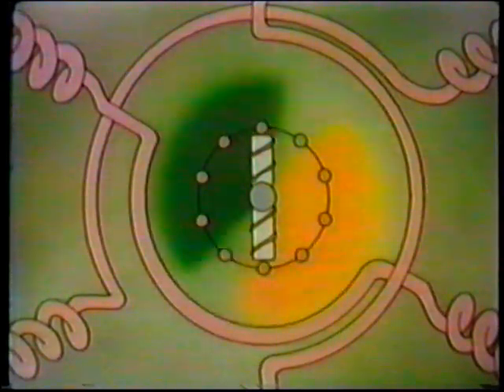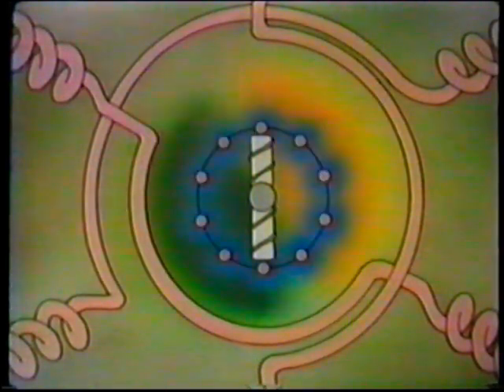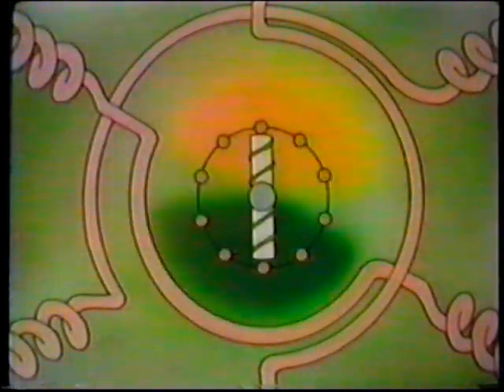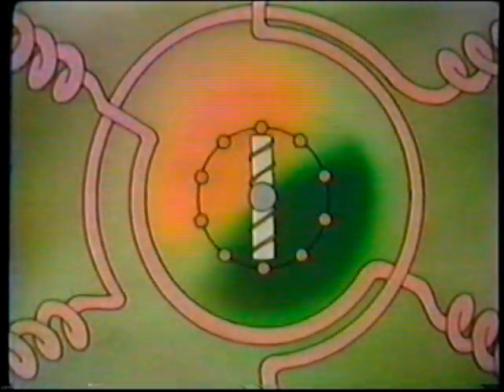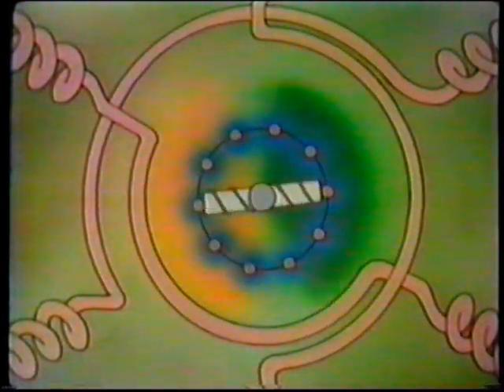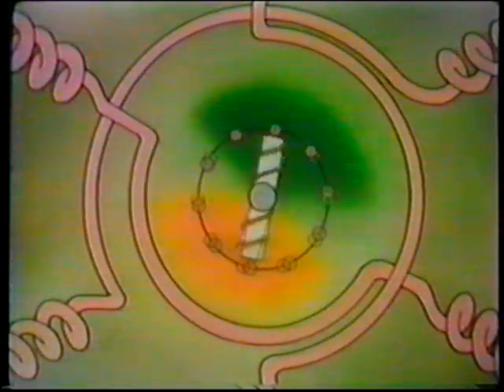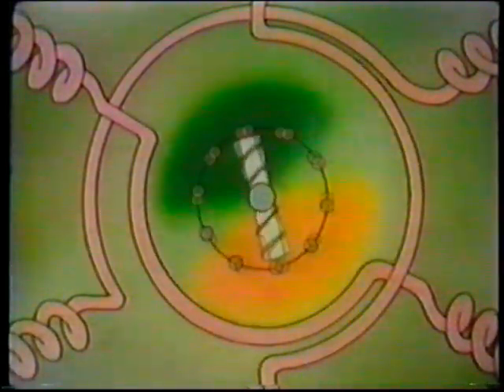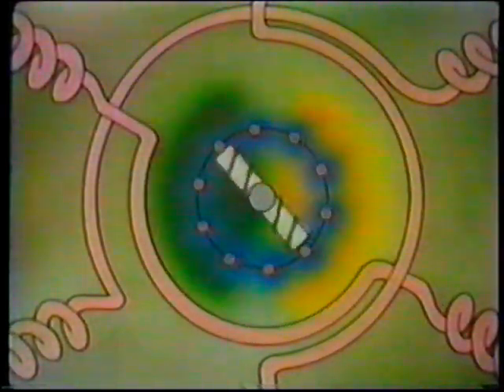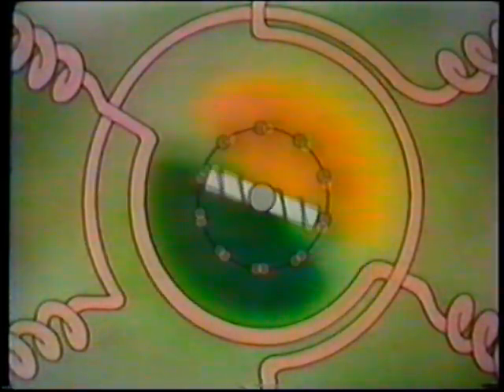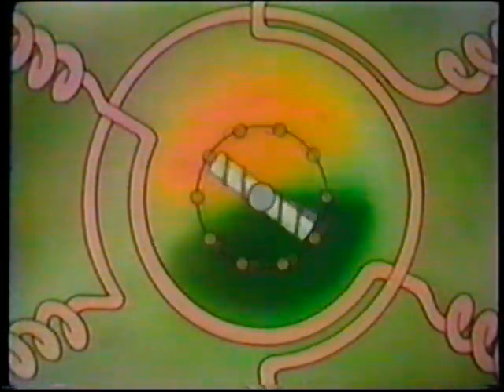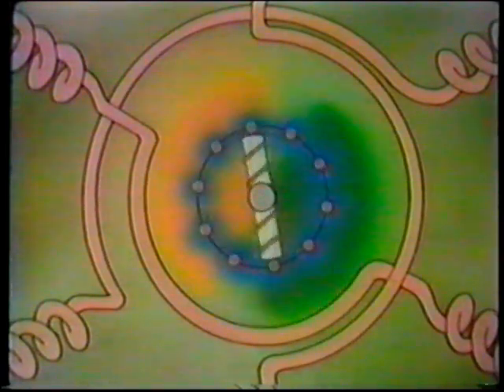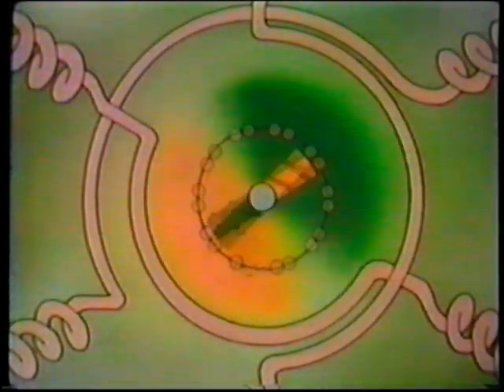The induced voltage causes alternating current to flow through the amortisseur bars, and a magnetic field is produced. The amortisseur bar's magnetic field interacts with the rotating field of the stator and causes the rotor to turn. As the rotor accelerates, relative motion between it and the stator field decreases. When the rotor reaches a speed close to synchronous speed, the rotor windings are energized with direct current.